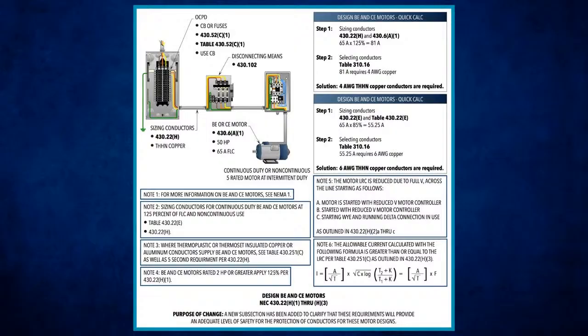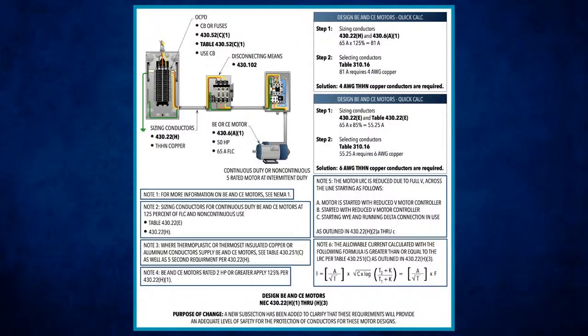Okay. Now, have you ever looked at an AC unit nameplate where it had minimum and maximum breaker size? 100%, I've seen that. Okay, now if that's the case, Jeremy says there's no such thing as a minimum, but yet you've got a manufacturer that has a starting point there that tells you it's got to be this size. He's not saying you can't go lower than 175%. Matter of fact, I just said you could. I said it's a starting point, Jeremy.